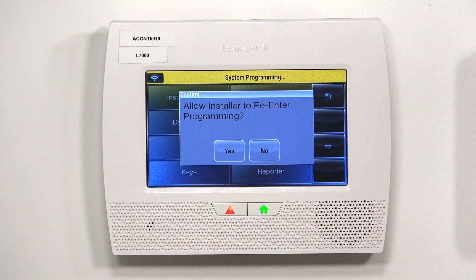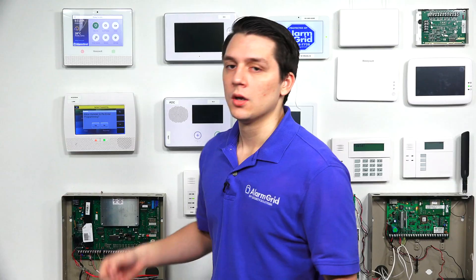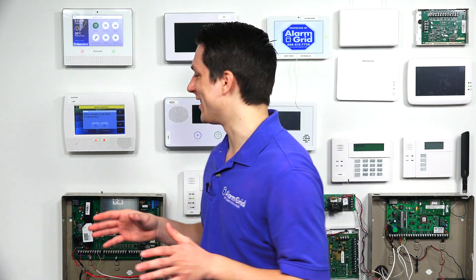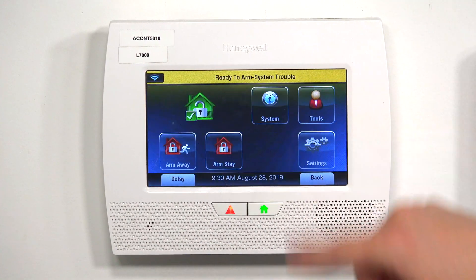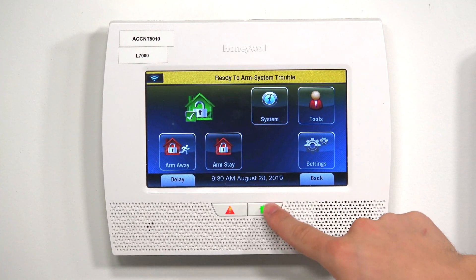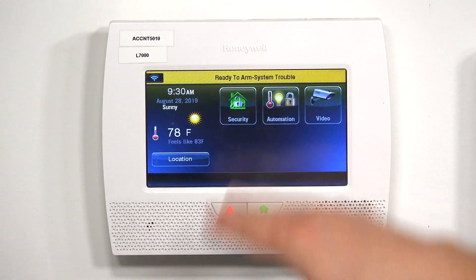You'll normally get a window that says "Allow installer to re-enter programming." Always press Yes — always. If you ever press No, you're going to lock yourself out of programming and you'll have to try to backdoor the system to re-enter it. So to avoid all of that, just tap Yes. Then hit the back arrow and the home button, and now you're back at the main menu.